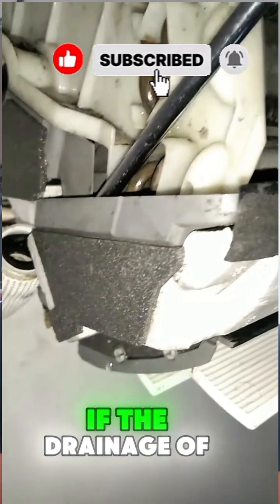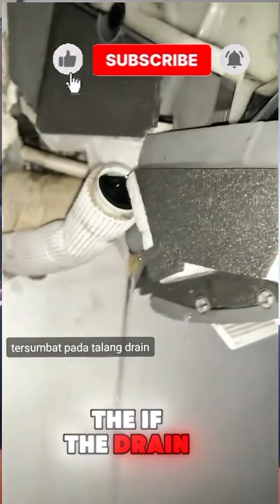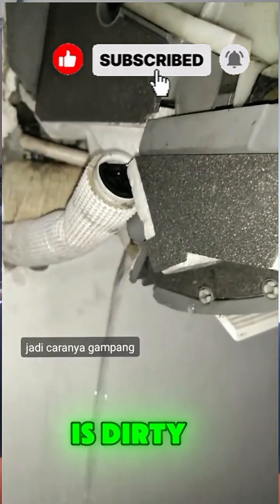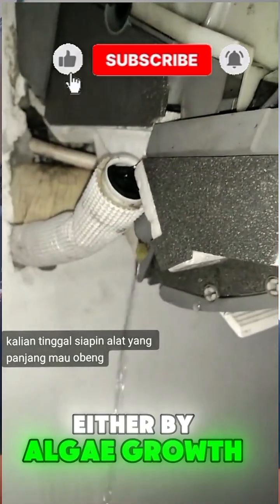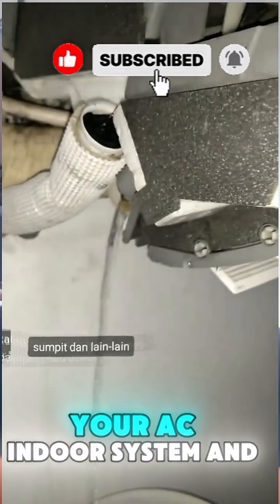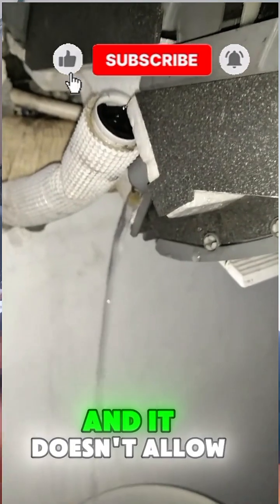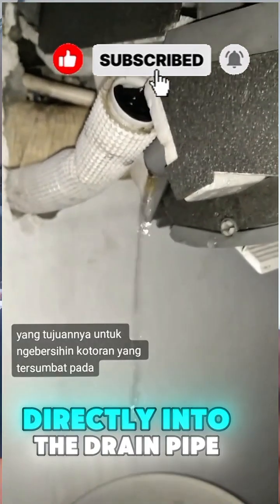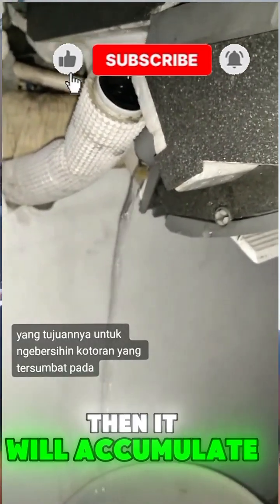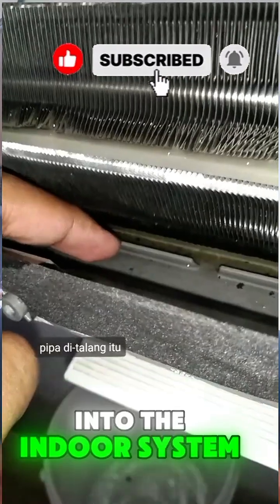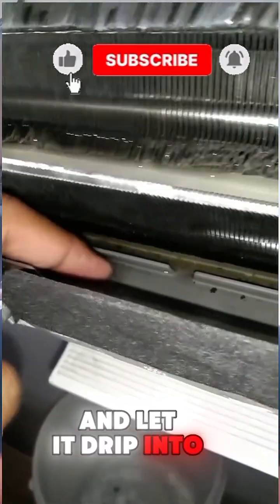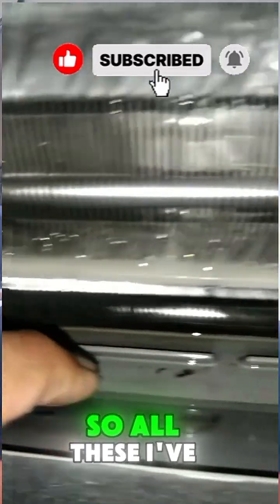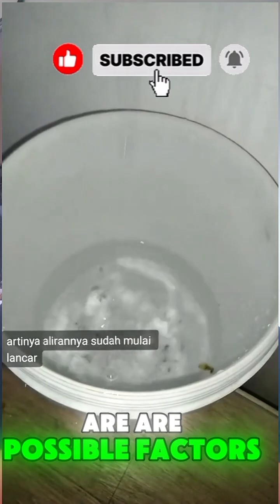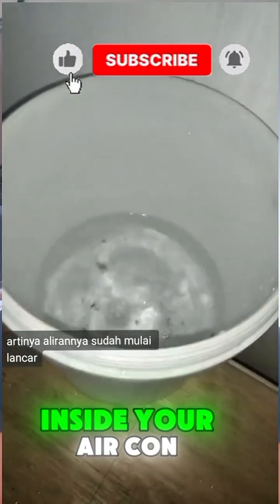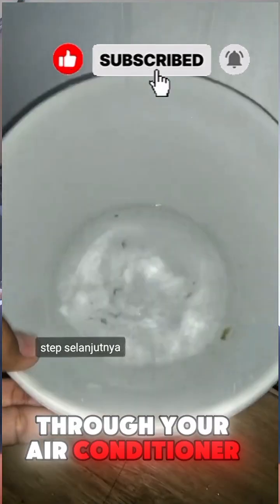Another thing that could cause your AC to keep dripping water in your room is a dirty drainage. If the drain system of the AC is dirty, either by algae growth, if algae grows in your AC indoor system and doesn't allow your water to flow directly into the drain pipe, then it will accumulate the water in the air condition, in the indoor system, and let it drip into your room. So all these I've just mentioned are possible factors that could cause water dripping inside your room through your air condition.